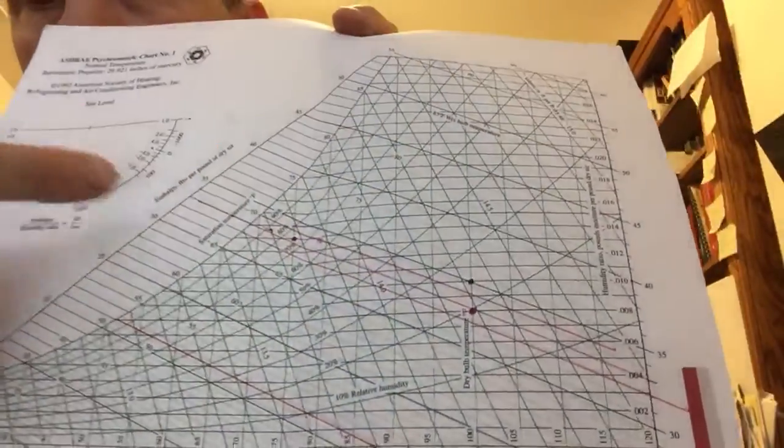Okay, so what does that look like on the psych chart? What you want to do is just imagine some sample of air that is not saturated, and then it ends up cooling, and that's exactly what happened. The air that's next to that glass started out maybe like 73, 74 in my room here, and then the air right next to the glass cooled, and eventually we got condensation. So cooling on the psych chart, remember the x-axis is our temperature, so cooling would be a process where we go to the left on the psych chart. That's what it would look like.